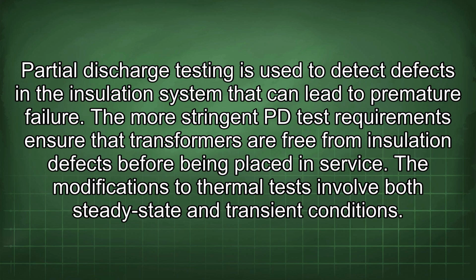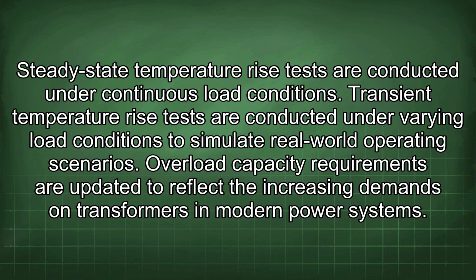The modifications to thermal tests involve both steady state and transient conditions. Steady state temperature rise tests are conducted under continuous load conditions. Transient temperature rise tests are conducted under varying load conditions to simulate real-world operating scenarios. Overload capacity requirements are updated to reflect the increasing demands on transformers in modern power systems.